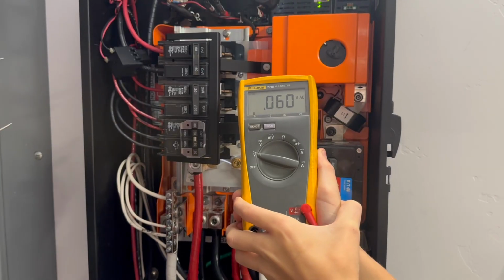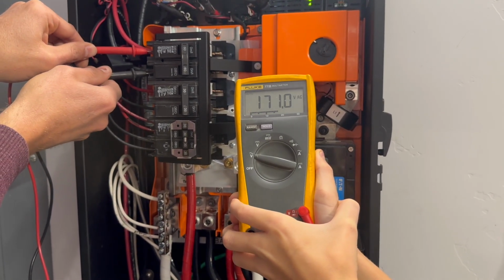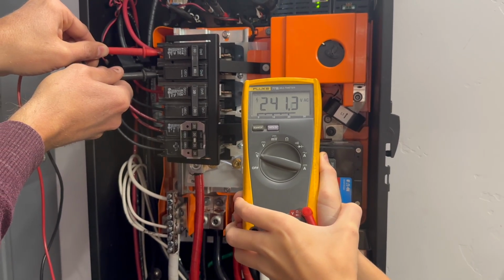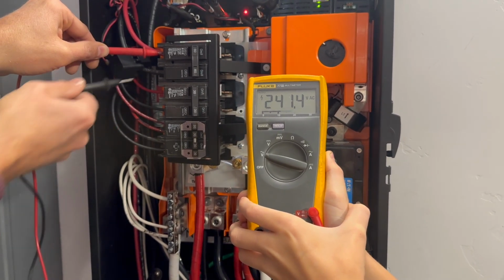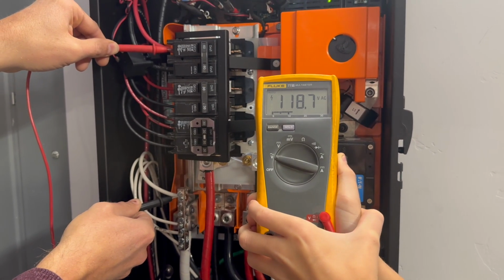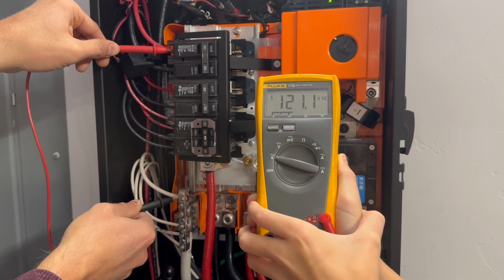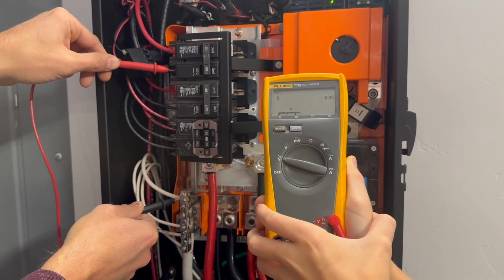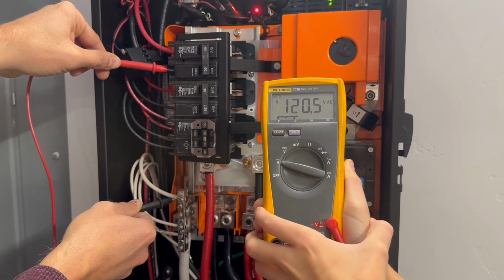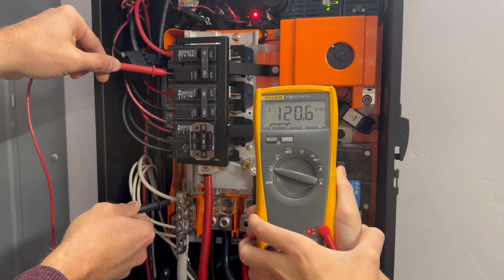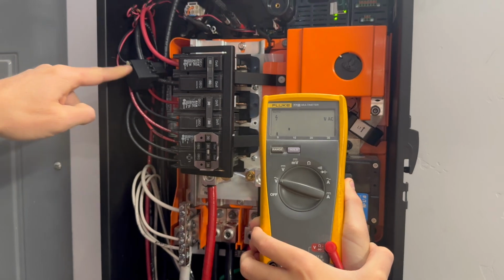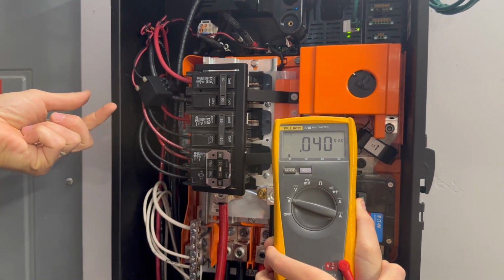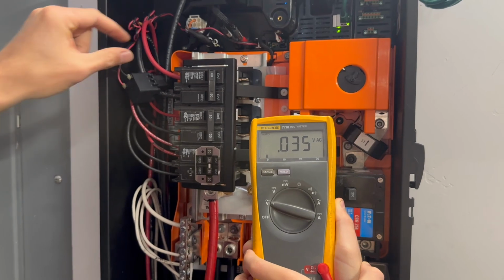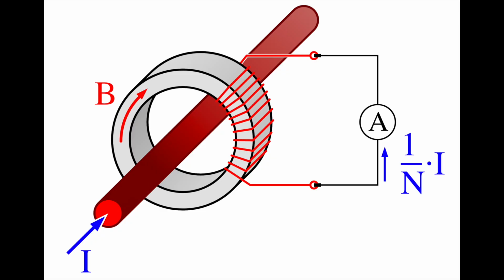This is because the red and the black wires coming from the solar are together carrying 240 volts when you measure between them. While one wire is pushing current, the other is pulling back and forth. But if you measure either wire against the neutral wire in the system that they're tied into, each individually will be carrying 120 volts AC, in a sine wave 180 degrees out of phase with respect to the other. Flipping a CT around on the same wire also does the same thing. The sine wave basically shifts 180 degrees, and current flowing one way looks like it is flowing the other way with respect to the reference voltage. So if the CT is on the wrong phase with respect to the reference voltage, this could happen.